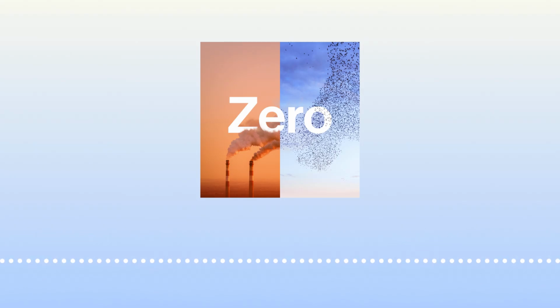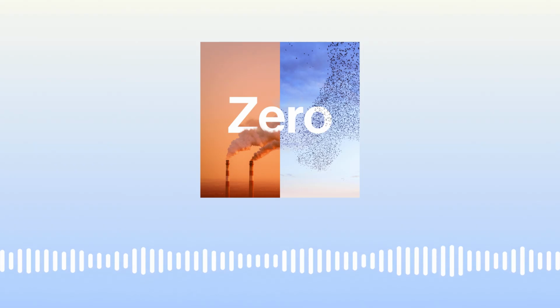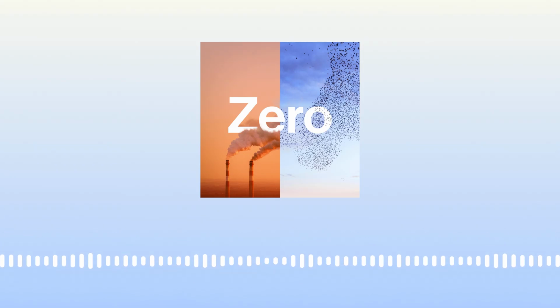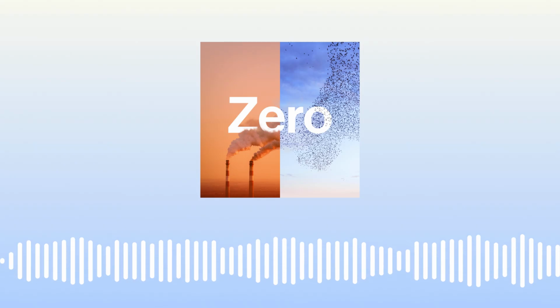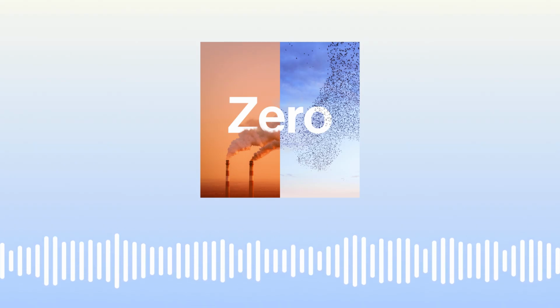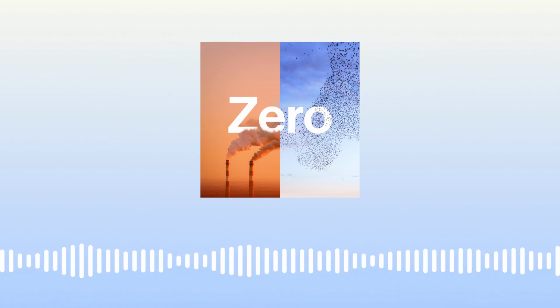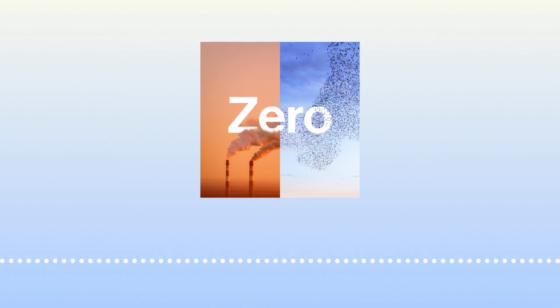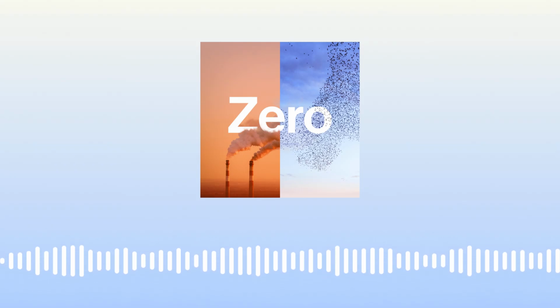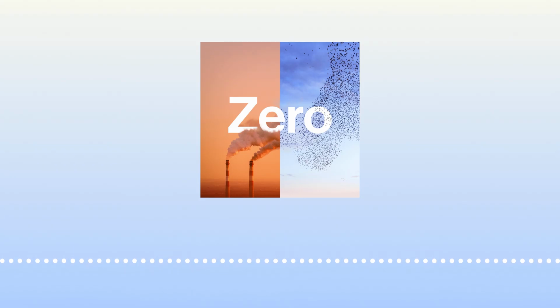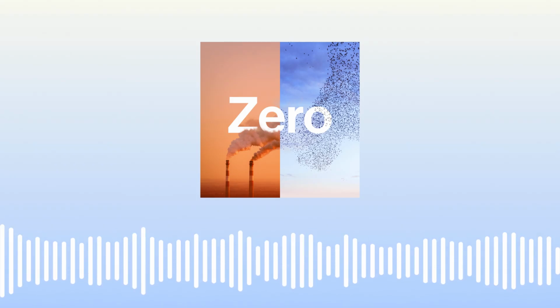Everything above that, or with a much higher power rating, you need to go DC, because there you don't have to charge and discharge. On top of that, DC also offers significantly less losses. It's also more advantageous in the grid because you have an inherent capability to control the power flow much better, to do emergency support if the grids are in a constrained situation. You can even, with DC systems today, do islanding, or what we call black start, to start up a grid that is completely dead or has suffered a massive failure, through these DC cables and DC converter stations.